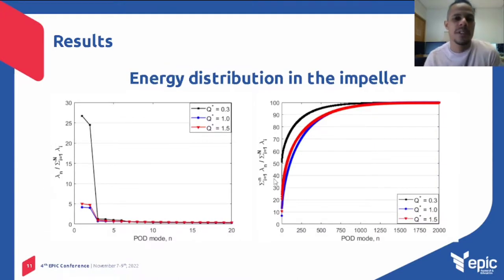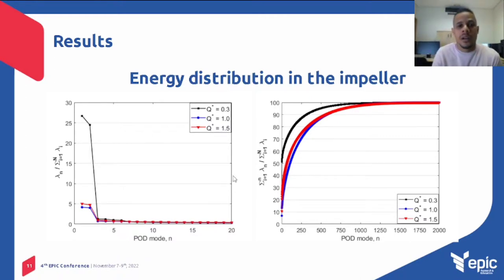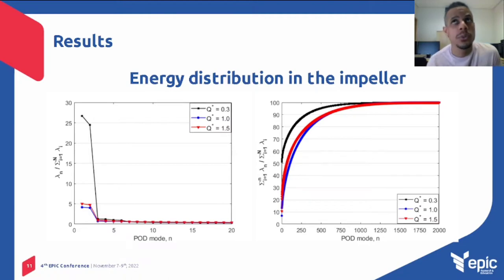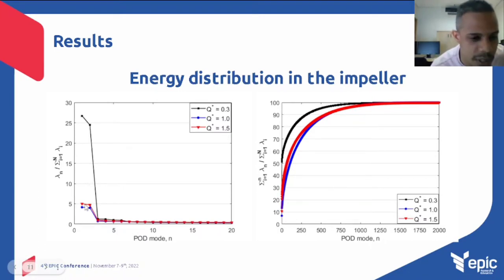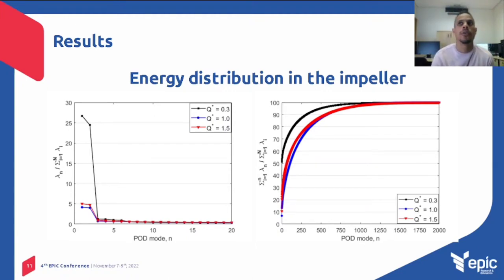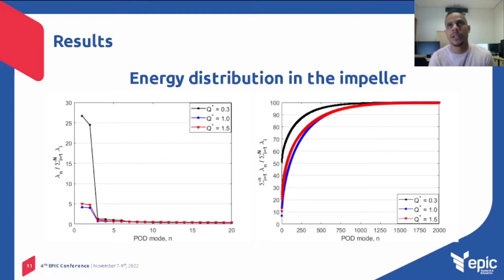Here I present the POD analysis results of the work. For the 0.3 BEP condition, presented here in the black curve, 50% of the turbulent energy is contained in the first two modes. For the 1 BEP, presented in the blue curve, and 1.5 BEP, presented in the red curve, the first two modes account for only 15% and 27% of the total turbulent energy. This is an indication that for low flow rate, the flow is dominated by large-scale turbulent structures — that is, coherent flow structures.